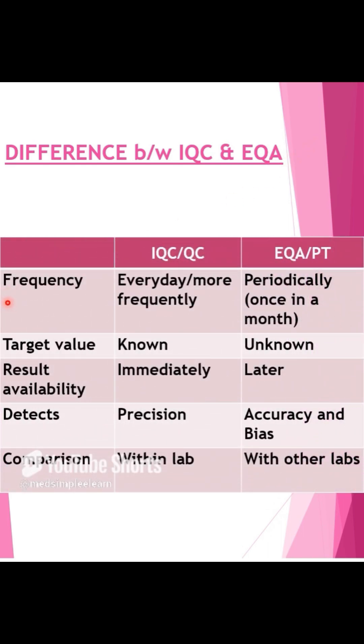Hello friends, through this short video let us understand the difference between IQC, that is internal quality control, and EQA, that is external quality assessment. The first difference is frequency. Depending on the sample load of a laboratory, IQC is generally done once, twice, or thrice a day — that is, frequently — while EQA samples are generally run periodically, once in a month.